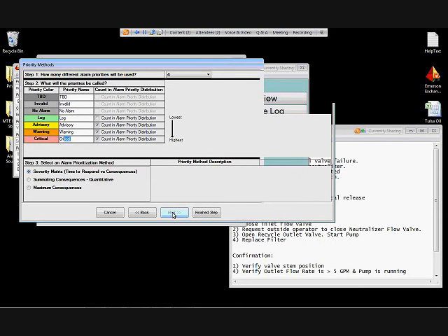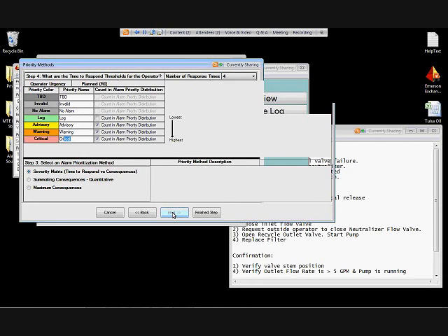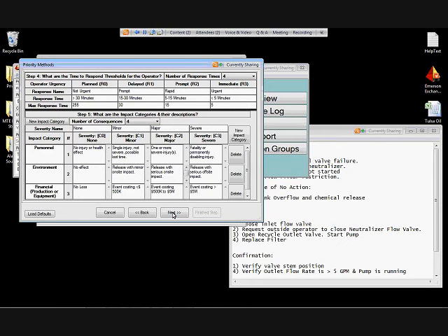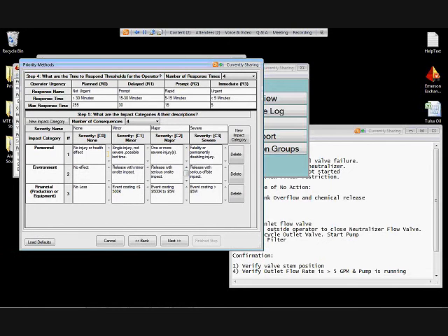So that matches up. Let's also look at the descriptions of consequences and impacts. The philosophy defines a consequence matrix of 4 columns by 3 different impact categories: personnel, environmental, and financial. That matches up, and we can see there are individual editable descriptions for each box in that matrix, which also corresponds to what's in the philosophy document.